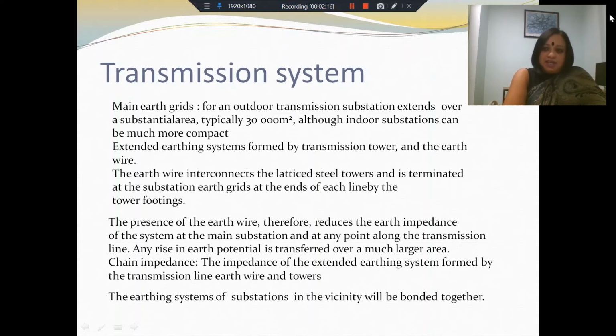Therefore, any rise in earth potential will not happen between two specific points. It will become distributed over a large area. So you will have a potential difference between two points, but that will not be between two points which are very close to each other; the same potential difference will extend over a very large distance. So that means the potential rise per unit length reduces. So this extended earth system is one way to reduce the earth impedance at any point in your system.